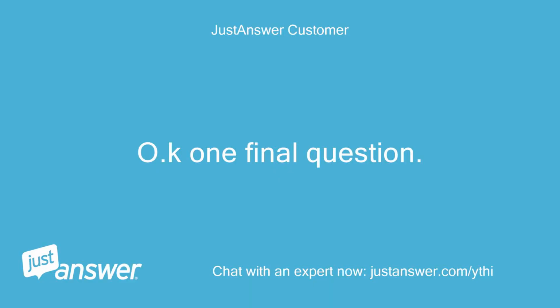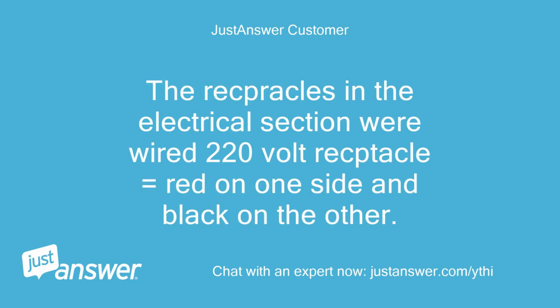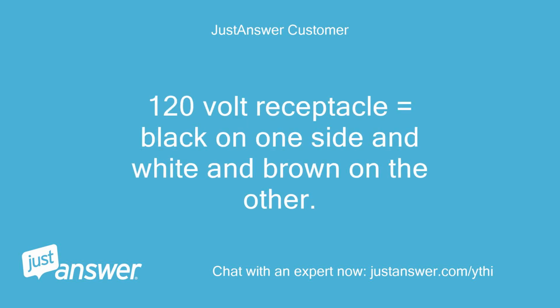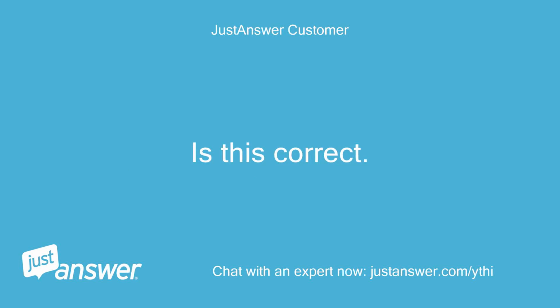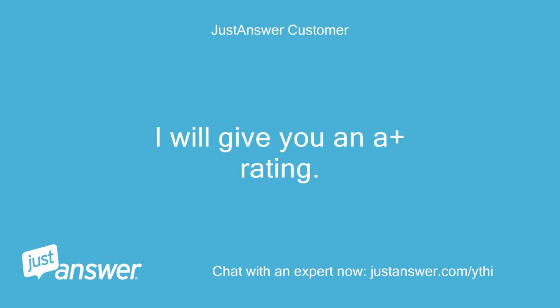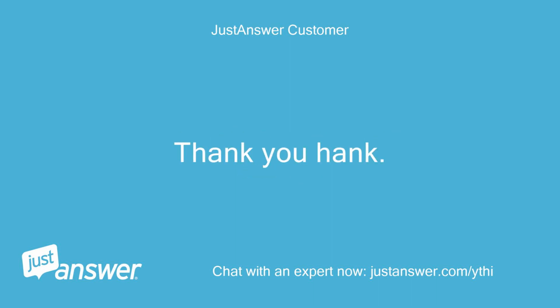Okay, one final question. The receptacles in the electrical section were wired 220 volt receptacle equals red on one side and black on the other. 120-volt receptacle equals black on one side and white and brown on the other. Is this correct? I will give you an A+ rating. Thank you, Hank.